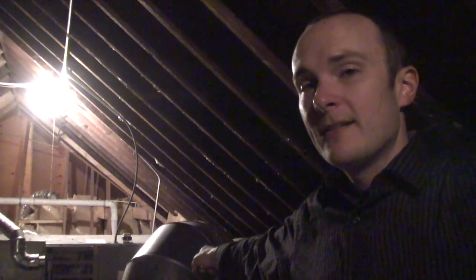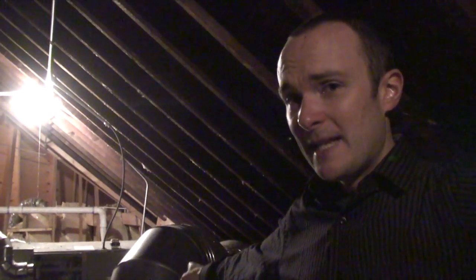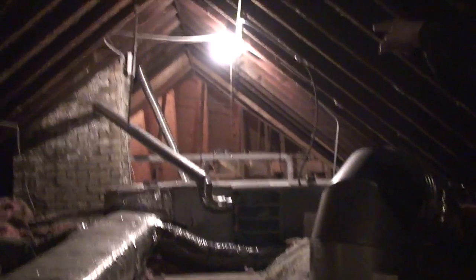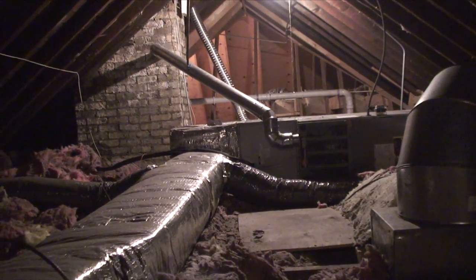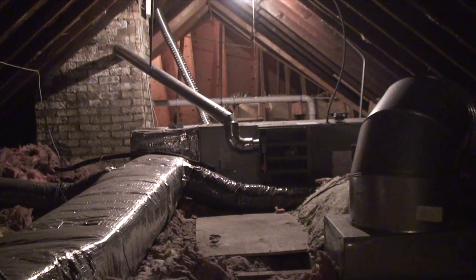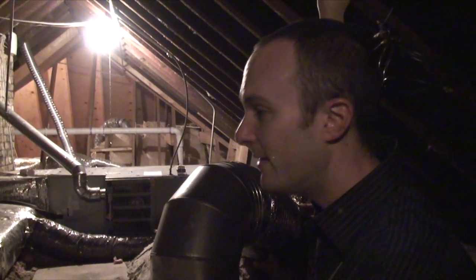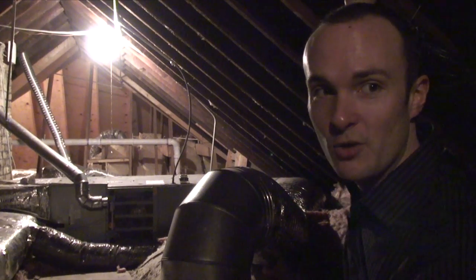We're going to want to seal the ductwork. You can see here that there's a huge section of ductwork that is totally uninsulated. This is the return side, but every bit of ductwork up here should be insulated — that's going to be the same temperature as the attic, which is going to be the same temperature as outside pretty soon. We also want to protect the exhaust fans. The inside of those is going to be all wet because it's hot, moist air inside there, and it's going to be 30 degrees out here, so you might have some staining around your exhaust fans in the bathrooms. We've also got jumbled insulation back there that needs to be set right. Once the air sealing and insulation are addressed in this attic, we hit the mechanical system as well — making sure the duct system is totally sealed and insulated. Then this is going to be a very high-performing house, because this space is over basically every bit of the second floor, and so it affects everything.